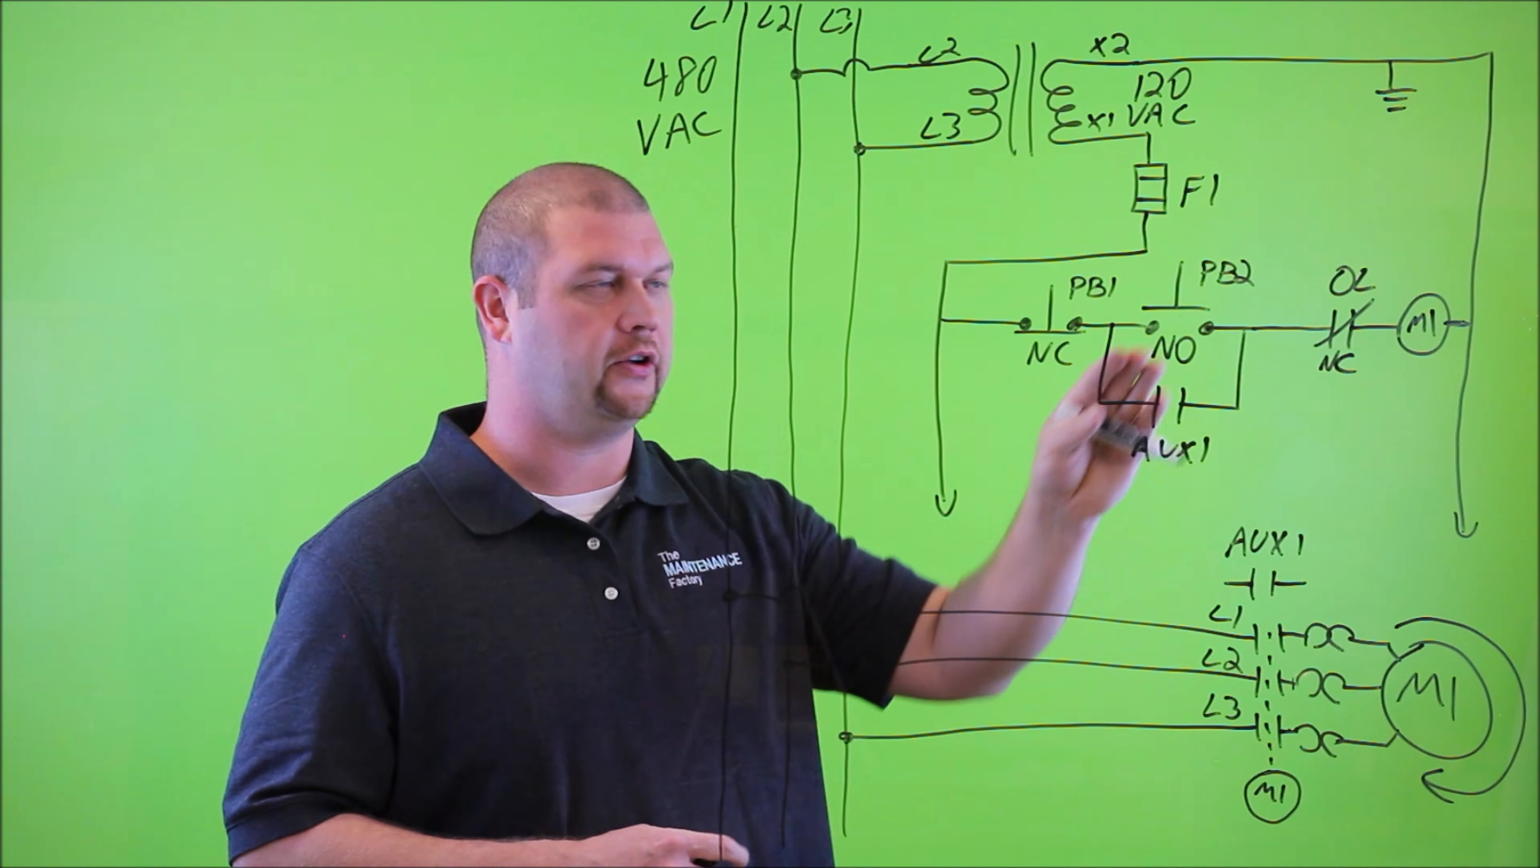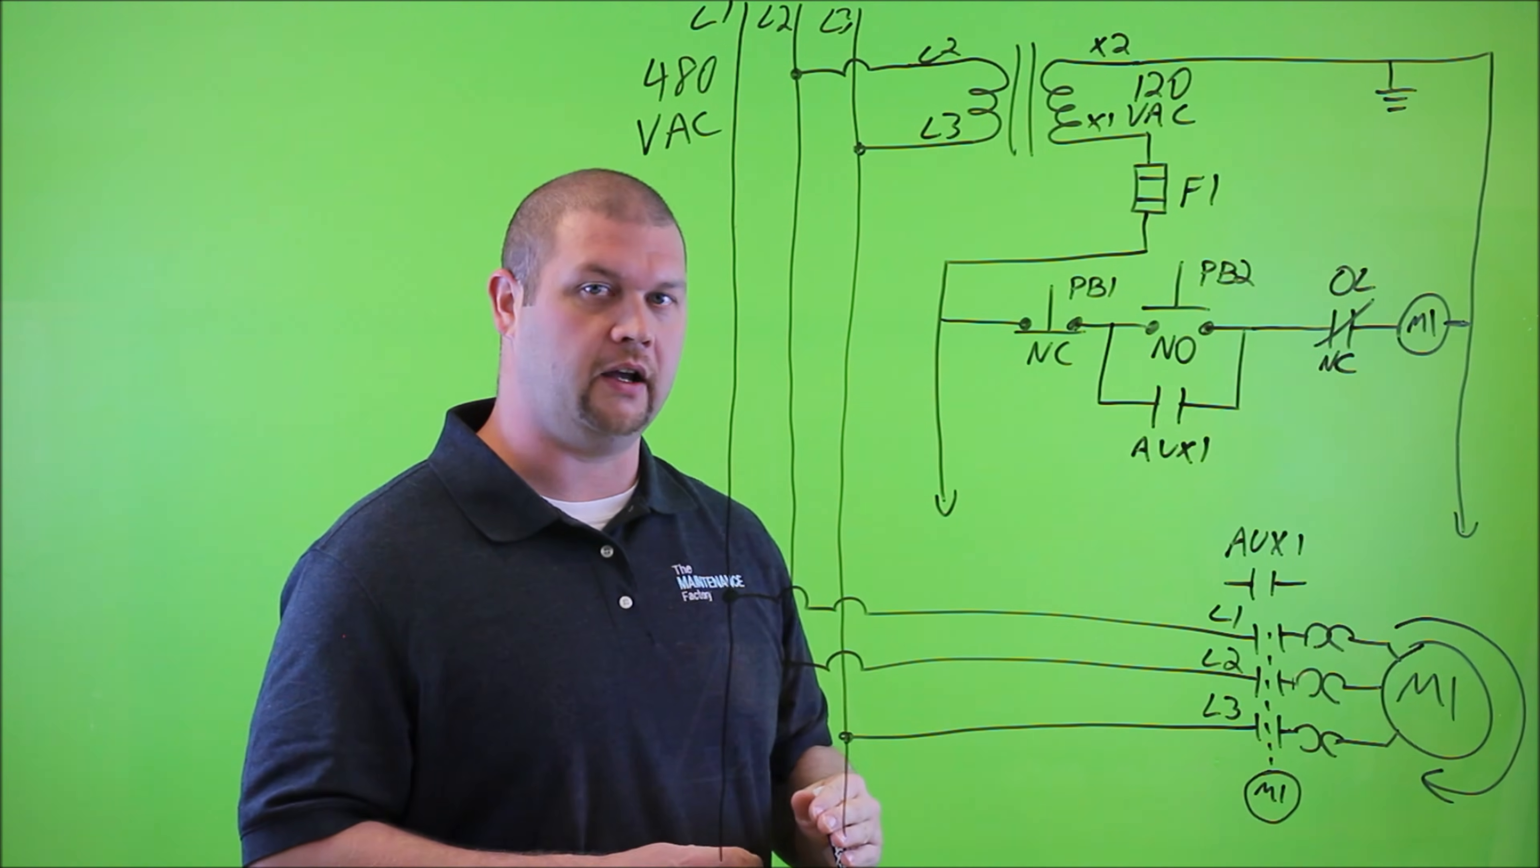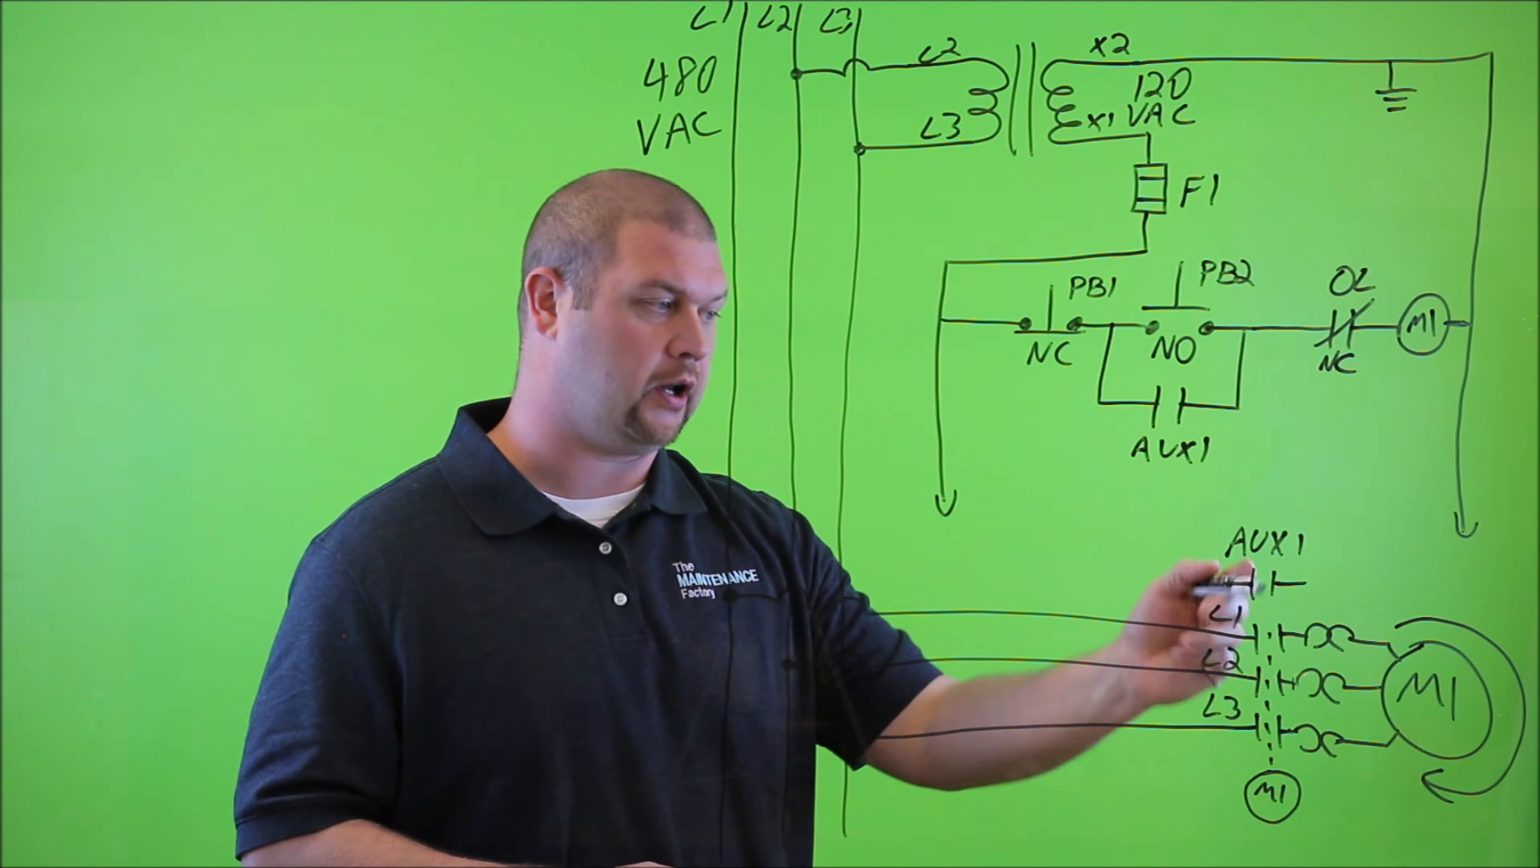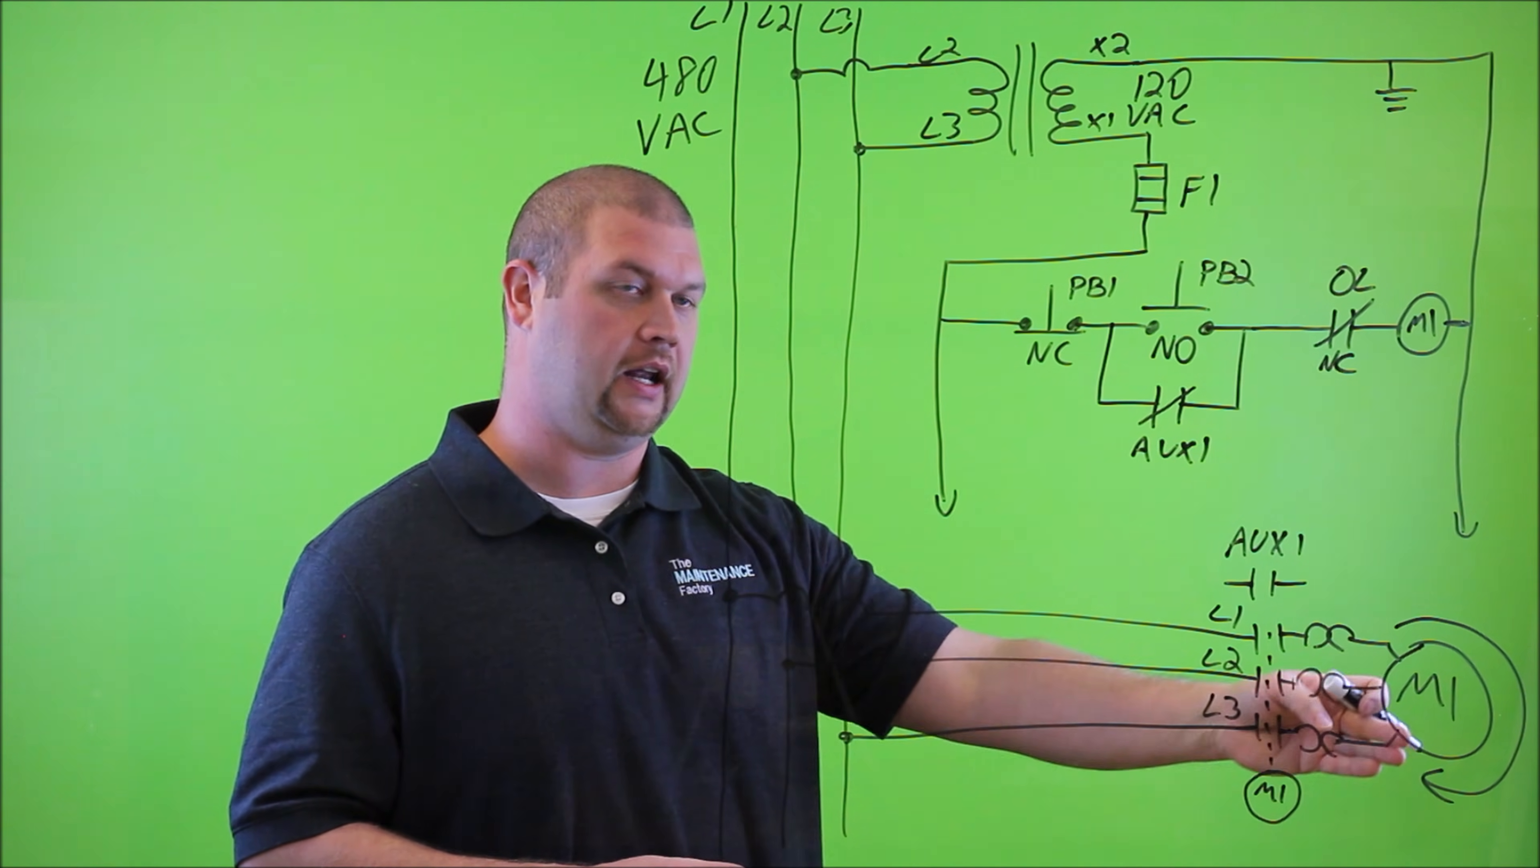So let's go back and review how this circuit would then work. So we would go back to the start button. We would depress the start button. Current would then flow across the circuit here, getting to the coil, energizing that coil, creating that electromagnetic field, thus closing these three contacts. Now, simultaneously, as these three contacts close, this auxiliary contact will close. So right here, that will go to a closed state. Now, at that time, the motor will obviously begin its rotation.